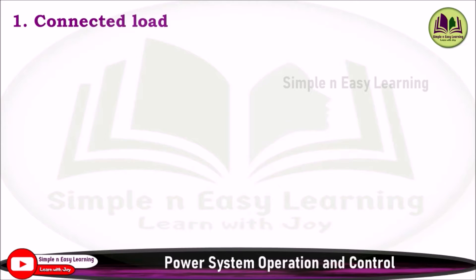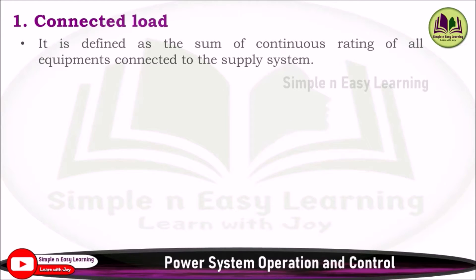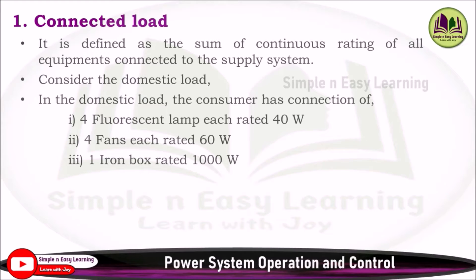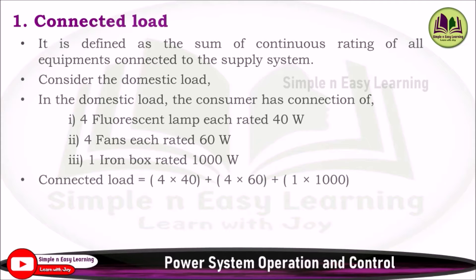First: connected load. It is defined as the sum of continuous ratings of all equipment connected to the supply system. For example, consider a domestic load where a consumer has four fluorescent lamps each rated 40W, four fans each rated 60W, and one iron box rated 1000W. The connected load is (4×40) + (4×60) + (1×1000) = 1400 watts.